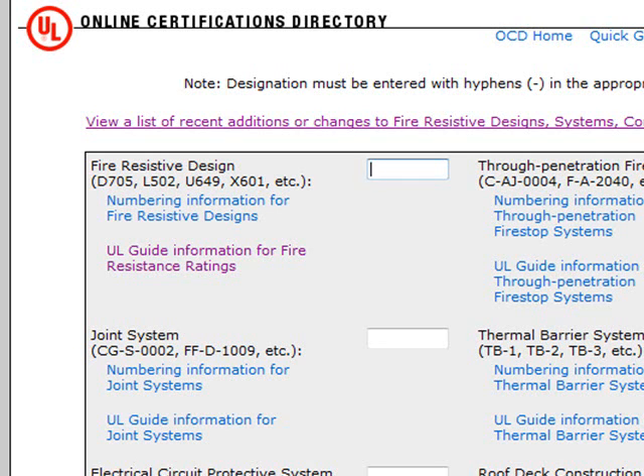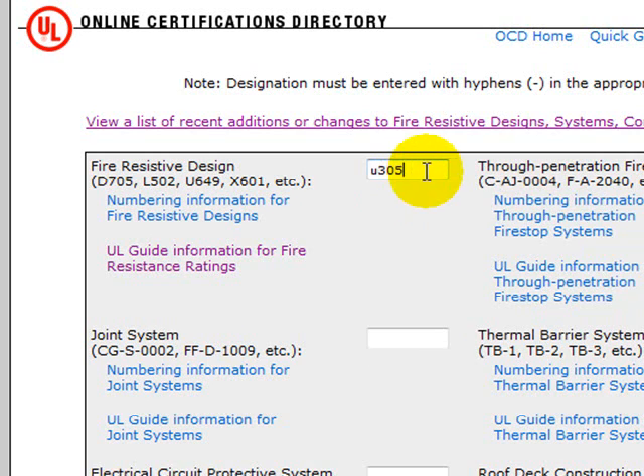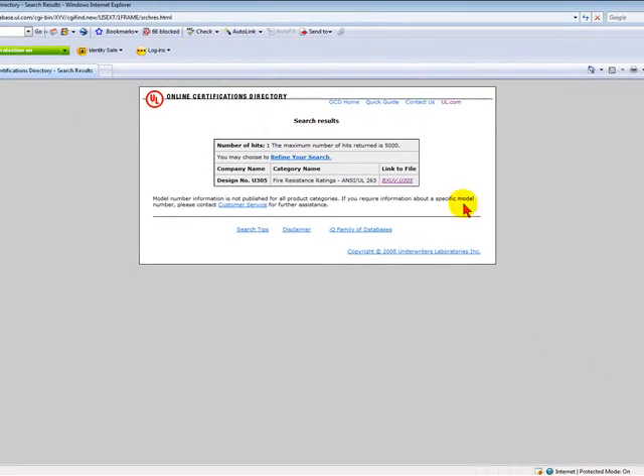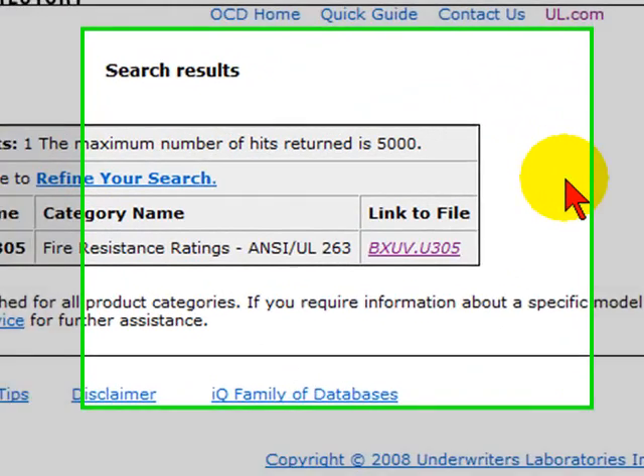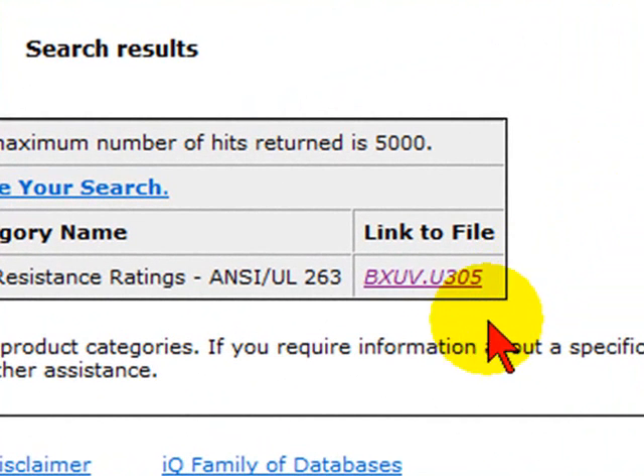In our example today, we're going to look at the specifics of a one-hour rated bearing wall. The UL, or Underwriters Laboratory, designation for this fire-resistant rated wall is U305, which we have obtained off of a set of plans we were reviewing for code compliance. Once we enter this number, U305, and press Enter, a new screen will come up showing the search results of this designation. On the right, you will see a link to the file.